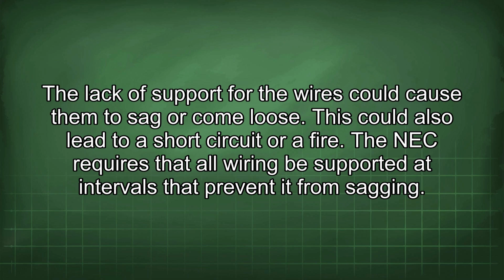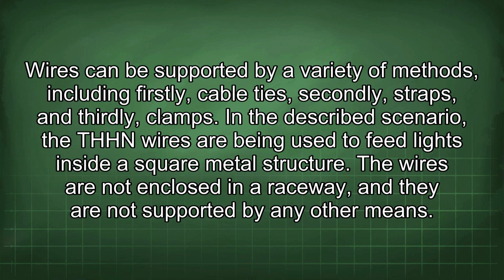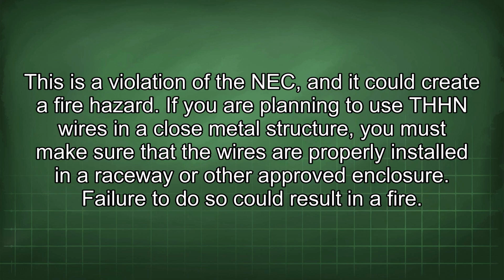The NEC requires that all wiring be supported at intervals that prevent it from sagging. Wires can be supported by a variety of methods, including firstly, cable ties, secondly, straps, and thirdly, clamps. In the described scenario, the THHN wires are being used to feed lights inside a square metal structure. The wires are not enclosed in a raceway, and they are not supported by any other means. This is a violation of the NEC, and it could create a fire hazard. If you are planning to use THHN wires in a closed metal structure, you must make sure that the wires are properly installed in a raceway or other approved enclosure. Failure to do so could result in a fire.